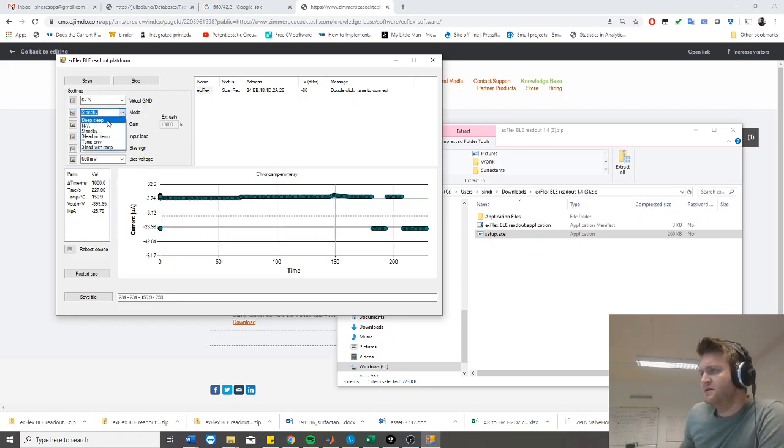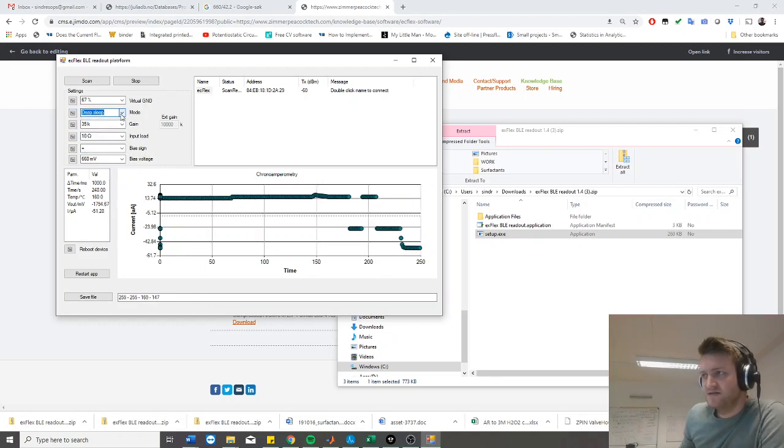And you have deep sleep, which basically puts the potentiostat front end to sleep, and you can trust none of these readings. So if you want to further save power, this is the way to go. You can put it to sleep for, let's say, 5 minutes, then go back, do a reading, put it back to sleep as an effective means of power saving.